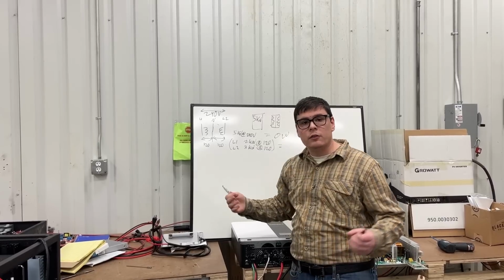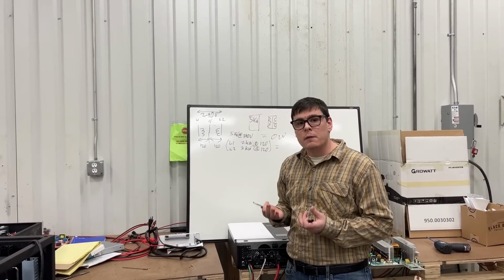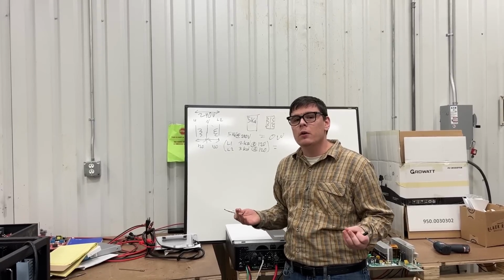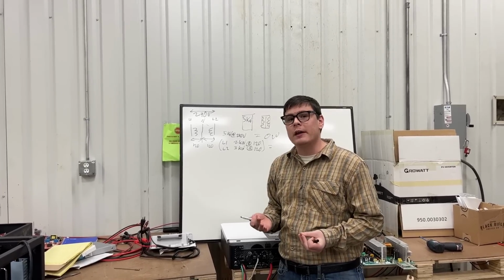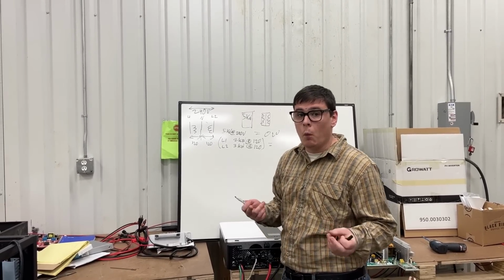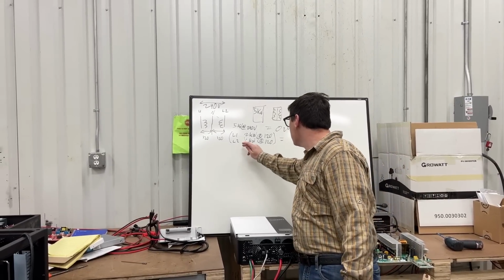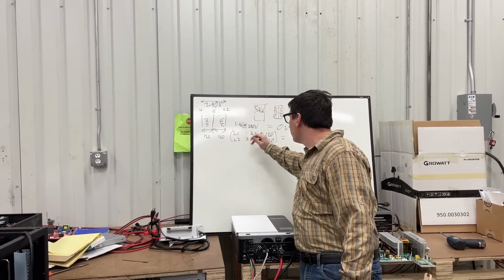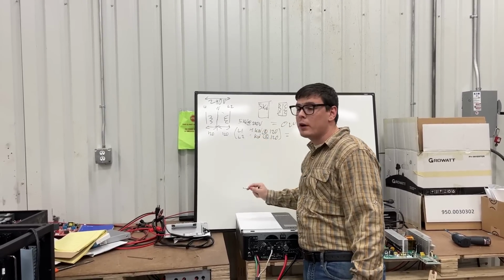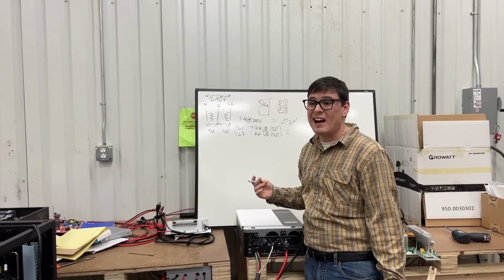The 2 kilowatts on line 1 and the 2 kilowatts on line 2 will combine together to make a 4 kilowatt 240. The transformer has nothing to do with the actual 4 kilowatts either. So that's not even material mathematically. It's the imbalance. Now yes, if you did not balance this, you could do 4 and you could do 1, which again, 4 kilowatts of 120 volt loads is kind of colossal for a continuous amount of time.